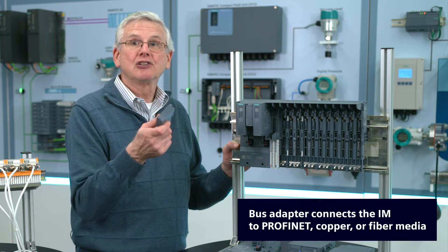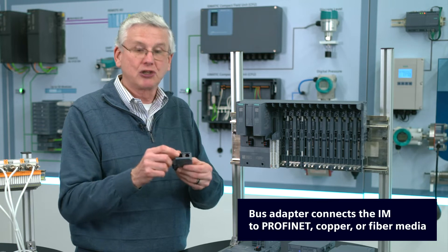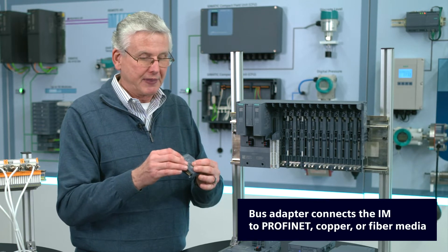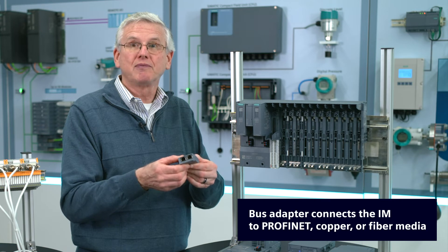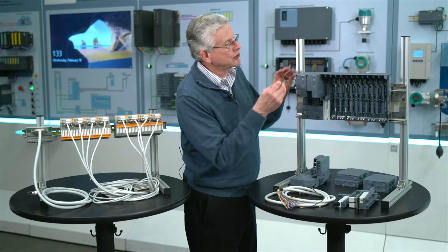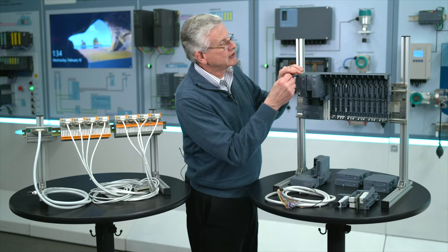Now I need a physical connection to PROFINET, and so we call that a bus adapter. So it's nothing more than a two-port switch. This particular one is RJ45. We also have ones that are fiber, and actually one that's fiber and copper. So literally what we need to do is plug that in. And this one actually has a little screw to make sure it stays in place.